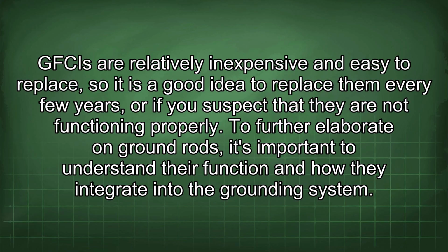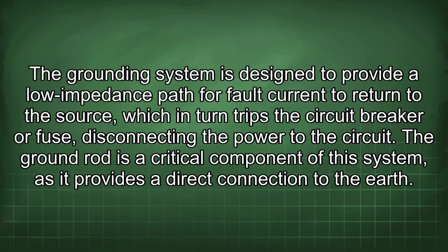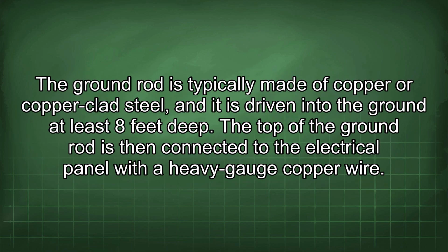To further elaborate on ground rods, it's important to understand their function and how they integrate into the grounding system. The grounding system is designed to provide a low impedance path for fault current to return to the source, which in turn trips the circuit breaker or fuse, disconnecting the power to the circuit. The ground rod is a critical component of the system, as it provides a direct connection to the earth. The ground rod is typically made of copper or copper-clad steel, and it is driven into the ground at least 8 feet deep.